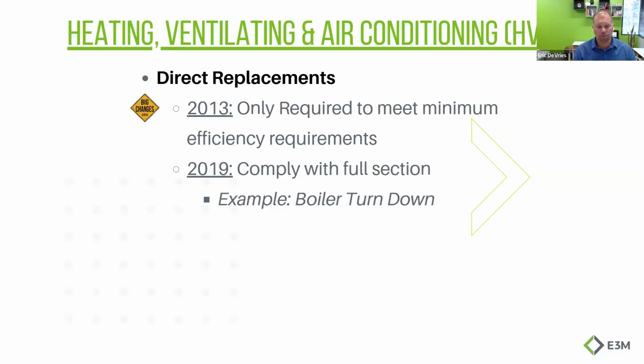So I give the example on the screen of a boiler, right? If you were doing a boiler project today, you could take out a 1,000,000 BTU boiler, put a 1,000,000 BTU boiler back, and you just had to meet the minimum efficiency, I think it was 96.2% or 92.6%. Now you have to add boiler turn down, you have to add outdoor air reset, you have to add some of these additional features that were required for new boiler systems, but were exempted under a direct replacement, are now required. Definitely a big change there for your HVAC service companies, for your fast track type projects, for, oh shoot, my unit died, I need to replace it because we're going into a holiday weekend and it's warm. You now have to look at some of these additional features that become required under this code.